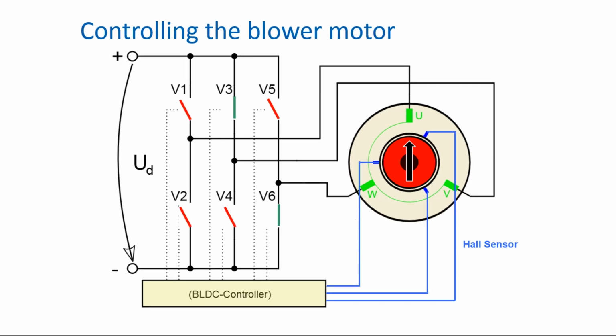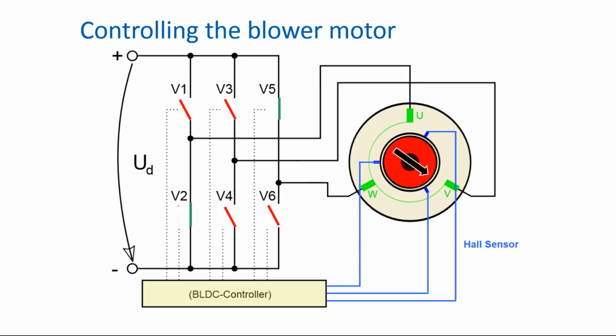Next, V3 closes to bring the current to V and W on the motor side, and through V6 back to ground. Finally, V5 closes and brings the power to W and U on the motor side, and back through V2 to ground. The same loop continues on and on, depending on the required blower speed.